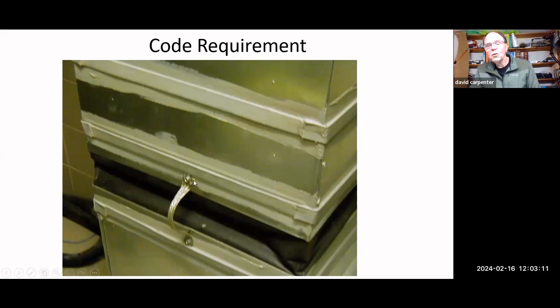This bonding strap is actually required by the manufacturer. It's put in with all of these larger HVAC systems, and even the smaller ones have them now. When you have a transition like this, you've got to bond it together so that it'll trip the breaker. You've actually lost your equipment ground when you don't put this in here. The manufacturer knows that. That's the reason they put them inside the equipment, so that you can use it, and they tell you to use it. This is the way it's supposed to be done.